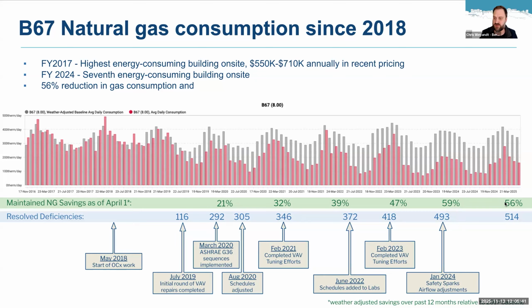As we've gone through further tuning of our systems, further adjustments of schedules, and in some cases adjusting airflow rates that were far above the requirements, we eventually got up to 59% natural gas savings. Now we've lost some of that over the past year due to some failures in our chiller plant, which is actively being worked on. But the red bars on this chart show the actual natural gas consumption over time, and the gray bars are weather adjusted baseline based on when we started in 2017.